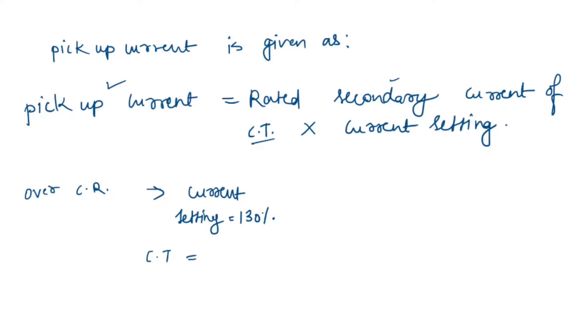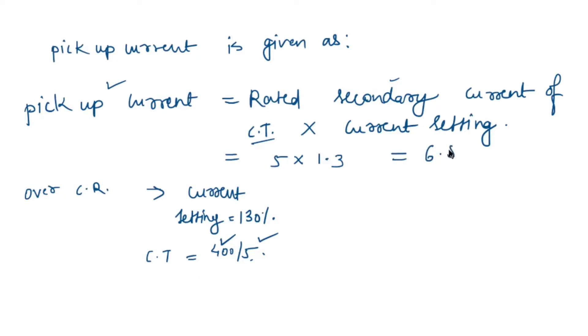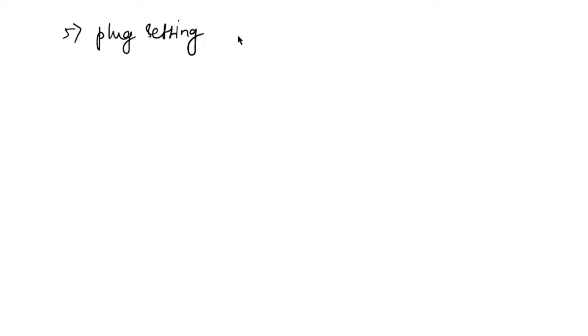The CT secondary side value is 5A and the primary side is 400A. The rated secondary current of the CT is 5A, and the current setting is 130%, which we convert to 1.3. Therefore, the pickup current equals 5 multiplied by 1.3, giving a total value of 6.5 amperes.